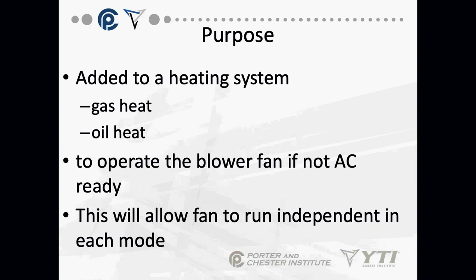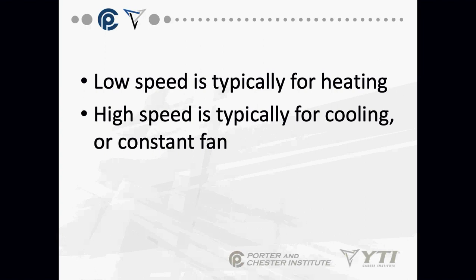Okay, a fan center is something we add to a gas furnace or an oil heat system to allow us to install air conditioning. Now, again, more and more, you won't have to do this because the equipment comes with the appropriate setup to run air conditioning. But the older style oil equipment, the older style gas equipment, was just set up to be a heating only system. The whole reason it's called a fan center is because our fan, our blower motors, are multi-speed. Okay, we have to be able to turn it on to high speed for cooling and low speed for heating. We have to be able to hit those two different speeds.